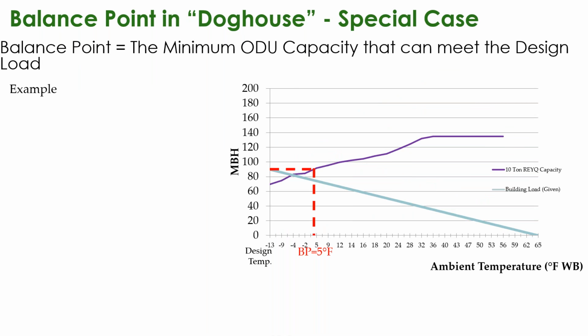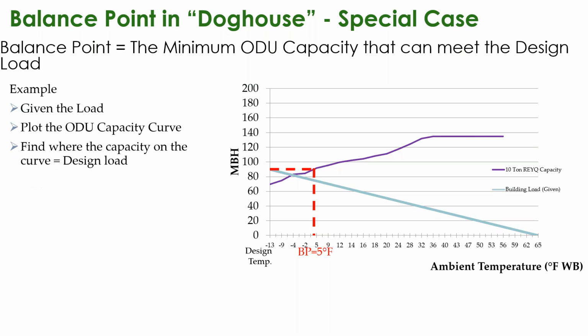So we'll talk more about these in depth as we talk about these cases one-on-one, but balance point for a doghouse application is a little bit of a special case. For balance point for the doghouse, the minimum outdoor capacity that can meet the design load is what you're going after, and that is not the point where it intersects, but that your outdoor unit is capable at some point of meeting that entire load. And again, you have to look at whether the juice is worth the squeeze given your load. Plot your outdoor capacity curve and find the point where it correlates to your load, and that is your balance point. So you can see here that is 5 degrees in this case of this 10-ton.